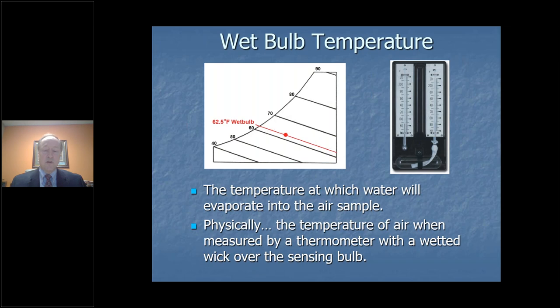As moisture is evaporating off of the wick, or that wet sock of the wet bulb, it's drawing some heat. You have to have heat to have a phase change from a liquid to a vapor, so it's drawing the heat out of that thermometer. And so the drier it is outside, the greater the differential will be between the dry bulb and the wet bulb temperatures. So let's say we've slung this around and we see there's a difference of 75 degrees dry bulb and 62.5 wet bulb. And then you would chart this out.